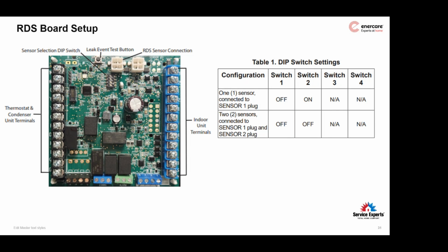All right, moving on. So now the RDS board itself can be mounted to a flat level surface within the length of the sensor cabling. For instance, I think Carrier's is 8 feet. I believe the sensor wiring for the Lennox stuff is also 8 feet. So just as long as it's within that 8 feet and you can get that drip loop in and the harness connected to the board, and as long as it's on a flat surface, you're okay. I might suggest keeping it off the ductwork, but I think Lennox's stuff said specifically you could connect it. I mean, verify, but I think they said you could actually put it on the ductwork if you had to, or right on the appliance, if that was one of the more suitable positions. Ideally, a flat wall would be fine.